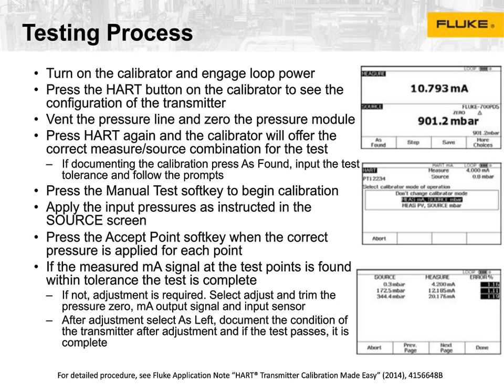Basically, at this point, you're going to vent the unit, and then you are going to press the Hart soft key again, and the unit, the 754, should give you the proper combination. You'll hit enter to select, and then at that point you'll hit enter again to select a linear instrument transmitter calibration. If it's set for square root output, you'll have to use the square root instrument button, and then at that point you can hit manual test, and it'll begin calibration.